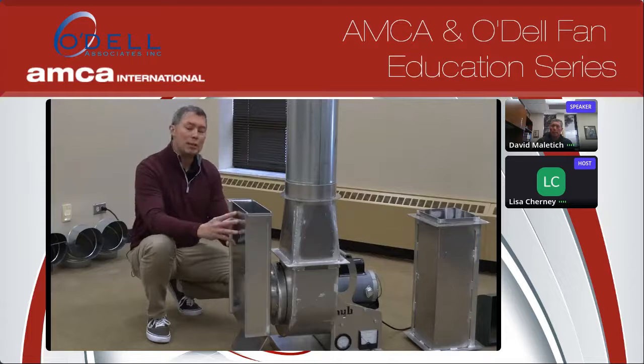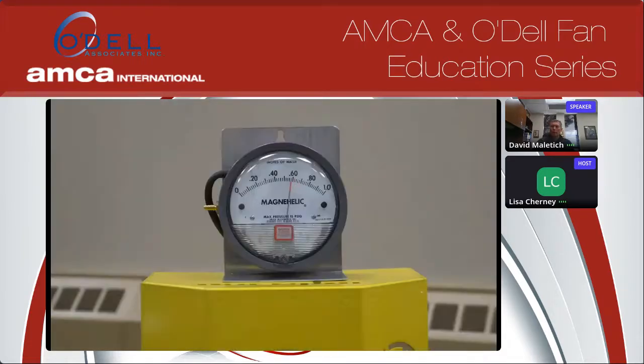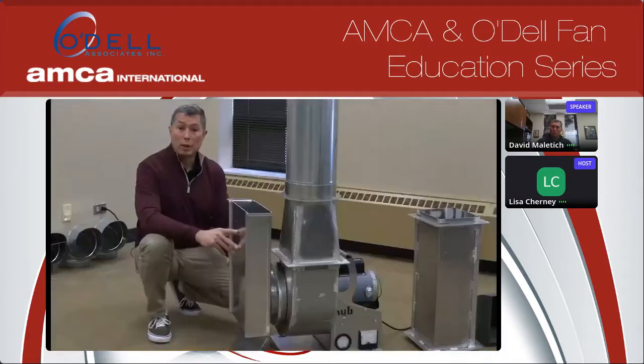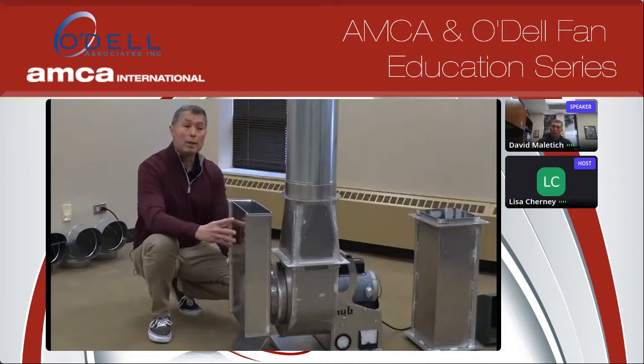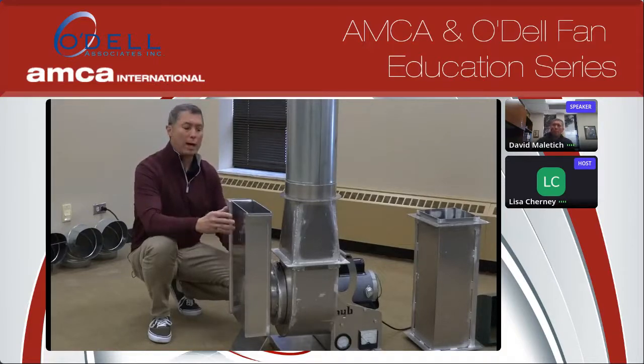And then secondly, if you have an application where you need smooth laminar flow going through it, like let's say a combustion air system, it's very hard to maintain a constant flame when the air is going up and down pretty consistently. The other thing is that when fans get very large, like a 200, 300, or 1,000 horsepower fan, that vibration can become pretty significant and actually cause ductwork to crack. It can also cause foundations to crack.